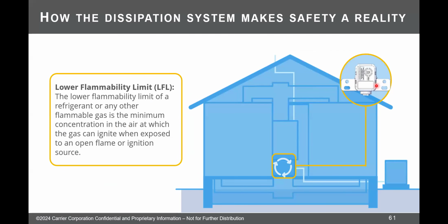The second half of that discussion is active dissipation. So active means there's going to be a sensor involved. Every single evaporator coil, there's one exception I'll mention later, but every single evaporator coil has to have a factory installed leak detection sensor on it. You're required to have that. They have to put it in there for you in the evaporator coil. So a rooftop has to have it, a commercial air handler, a residential air handler slash fan coil, an evaporator coil for a furnace. Whoever provides the evaporator coil has to give you this refrigerant leak sensor and any controls required to do the sequence I'm about to describe.